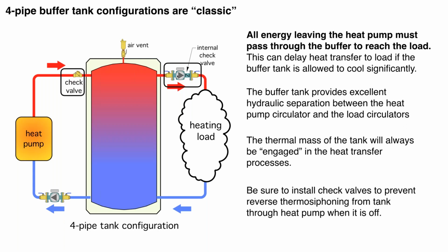Now, another important detail: anytime you have a warm thermal storage tank, and you have a piping circuit that goes from the upper portion of that tank to the lower portion, you really want to make sure you put a check valve in that circuit, because let's say we take this check valve away. What will happen is the warm water that's out in this pipe is going to give up heat. And as it gives up heat, it becomes denser, and as it becomes denser, it's slightly heavier. That's going to start to go backwards through this circuit if there's nothing preventing that. And ultimately, what you will get is called reverse thermosiphon. And over time, this will tend to dissipate heat from the tank.